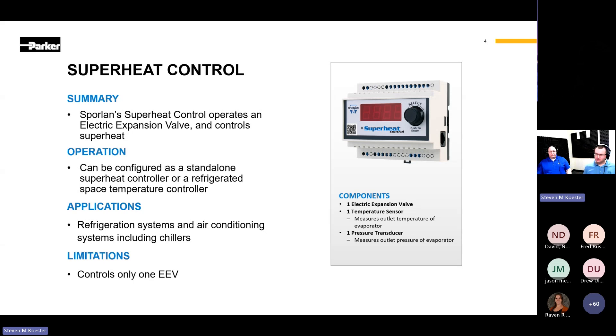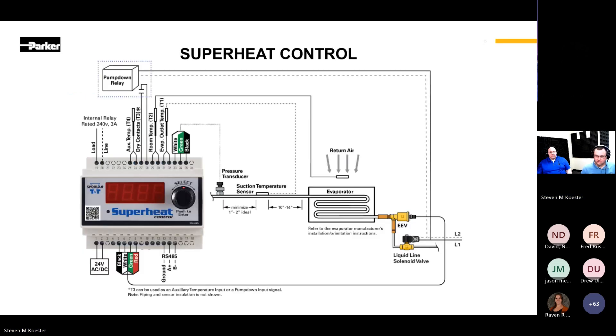We will start with the superheat controller, which is used to operate an electric expansion valve to control superheat, ensuring the liquid refrigerant is boiled off before it leaves the evaporator and heads to the compressor. Utilizing the inputs from the pressure transducer and temperature sensor, the controller uses algorithms to optimize the EEV's position to maintain the desired amount of superheat across the evaporator coil. Sporlan has a full array of electric expansion valves available to meet various load conditions in both residential and commercial applications. This diagram shows a typical installation for the superheat controller with pressure transducer and temperature sensor location after the evaporator coil.